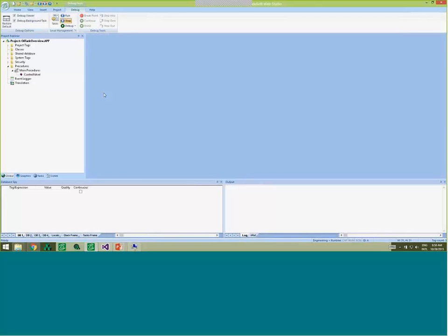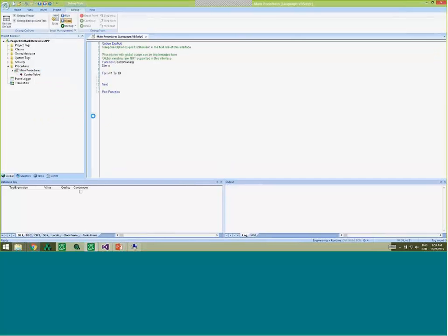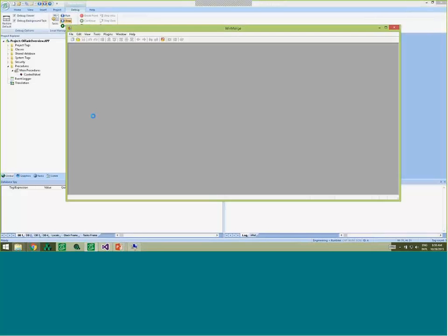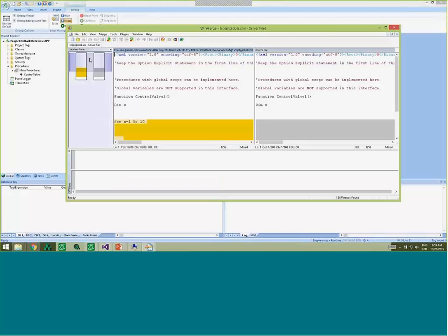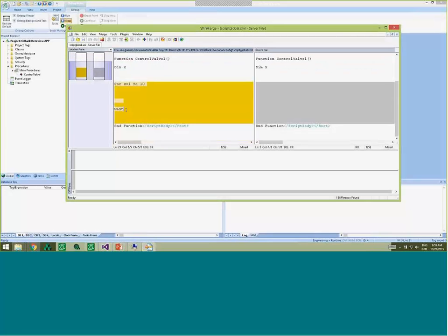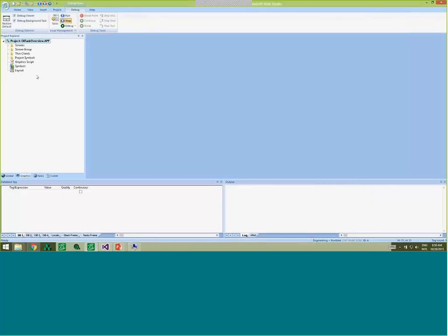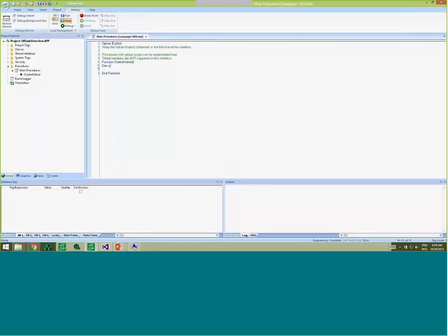But now I'm not 100% sure that the changes I made are correct. So again, I can right-click and say compare. WinMerge will open the two files side by side and highlight for you what the changes are. The change was that this portion of the code didn't exist before. Then you can either choose to continue and perform the check-in, or you can simply come back and say undo my pending change for that file. It will undo the pending change, and now it's going to show back the original condition.